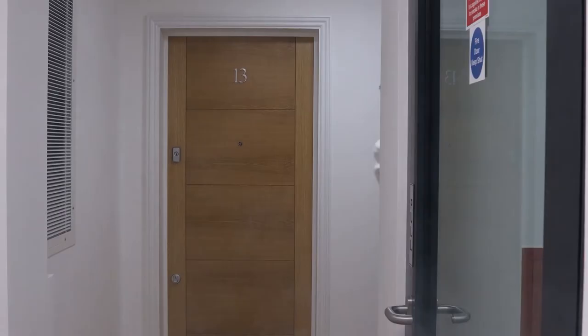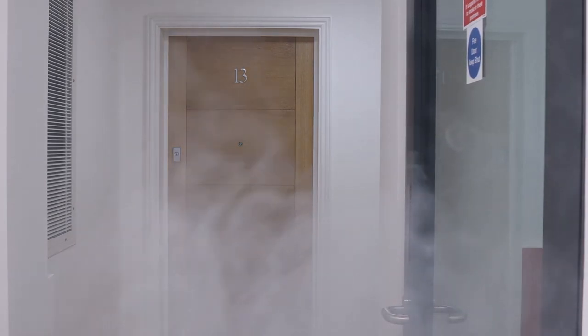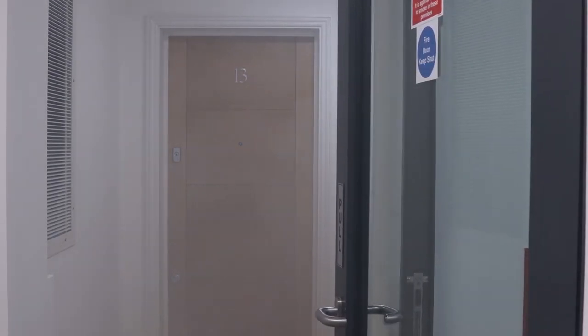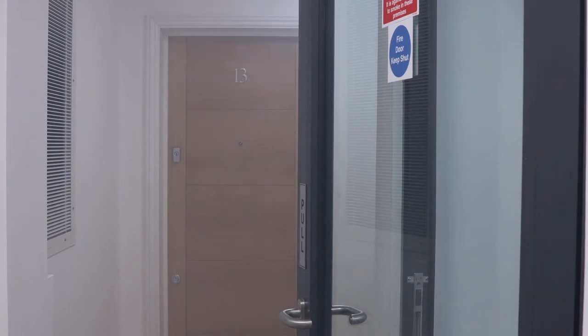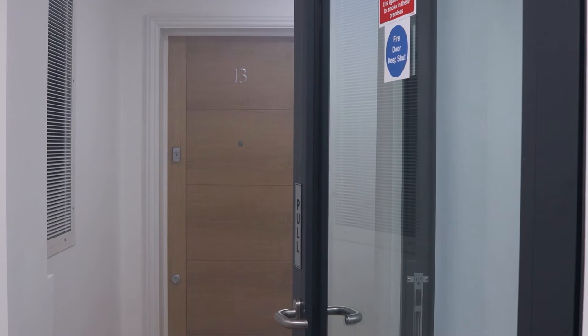Here's a short video to help illustrate everything. We can see first of all the smoke is beginning to build. The mechanical system starts up and you can see the smoke beginning to be extracted by the damper on the left hand side. On the right hand side the door is beginning to pull open. This is because the makeup air is coming from the head of stair vent and fresh air is coming down the stair core and being drawn into the protected corridor. We can see the smoke clearing quickly and there's no pressure build up across the doors of the apartments.